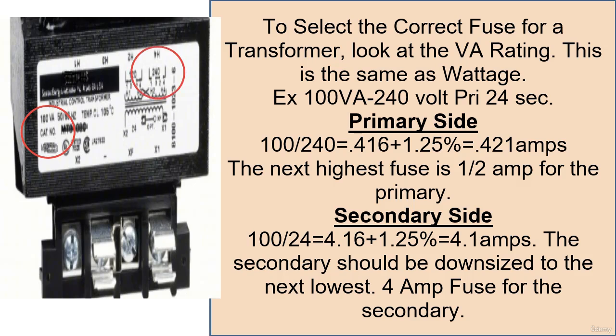An example, a 100 VA 240 volt primary with a 24 volt secondary. For the primary, you will do 100 divided by 240 equals 0.416 plus 1.25% equals 0.421 amps. You go to the next highest fuse, which is a half amp fuse for the primary. For the secondary side, you will do 100 VA divided by 24 equals 4.16 plus 1.25% equals 4.1 amps. The secondary should be downsized to the next lowest fuse, a 4 amp fuse for the secondary.